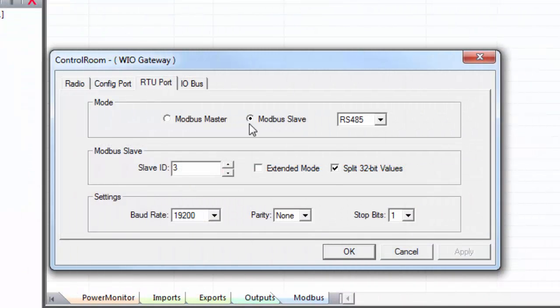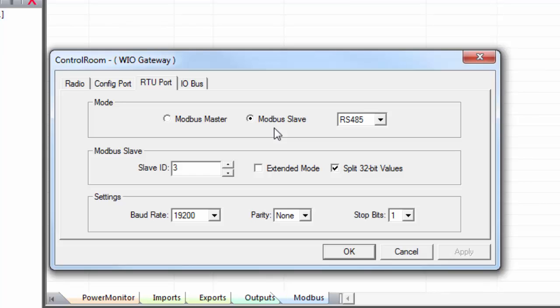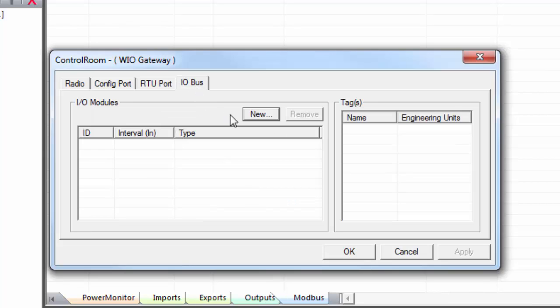You would set it to Modbus master if you want to use the gateway to pull registers from a device that it's connected to. And you would set it to Modbus slave if you have a PLC or an HMI or any other Modbus master device that's pulling data and you just want the gateway to act as a slave on the network.